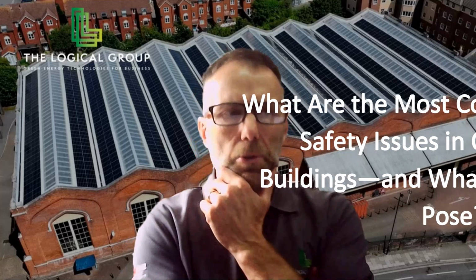Yeah, so I guess under the Electricity at Work Regulations and the Health and Safety at Work Act, it's important to make sure the electrical systems are safe. And the sort of things that we typically see could be anything from inadequate or out of date wiring or equipment, just things that are too old, improper earthing and bonding. We see a lot of that, where water mains, gas mains, etc., should be bonded and they're not. Missing or faulty RCDs, or when we test them, they're not operating correctly.